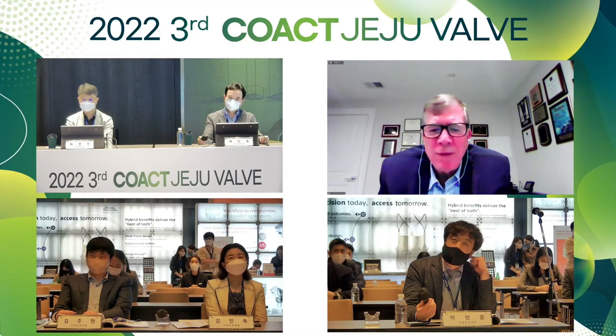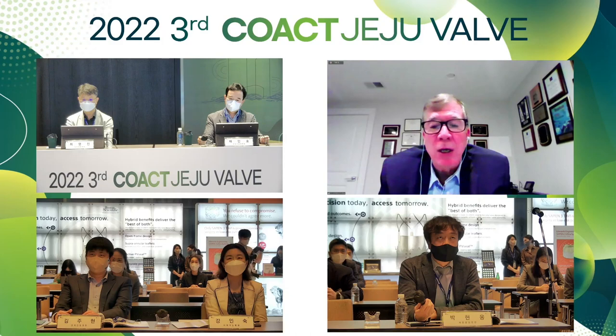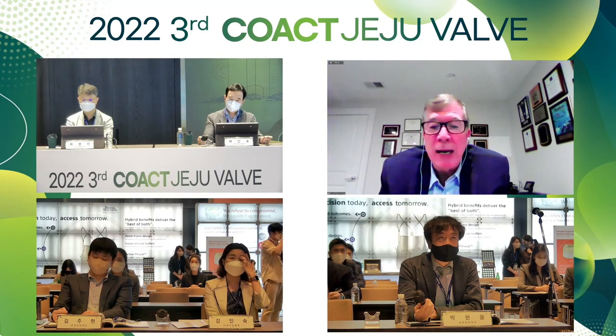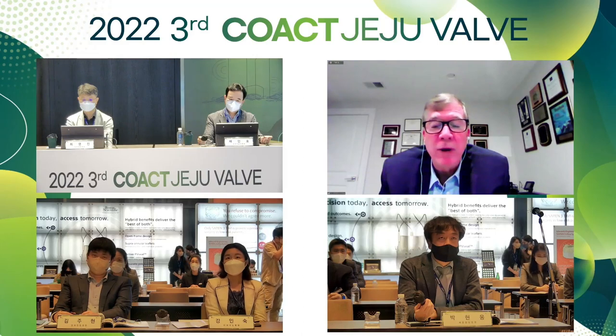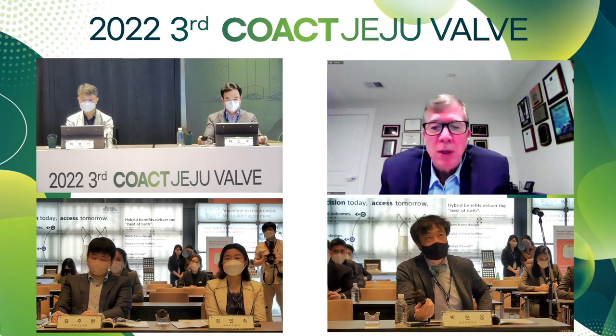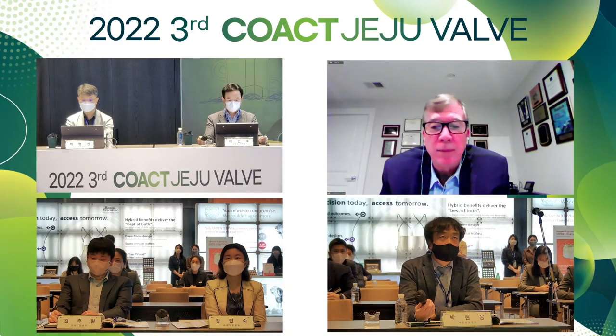Now, with respect to FX, there's not a difference in the profile, but there is a difference in the nose cone. So the nose cone now is like a dilator, like a sheath dilator, very smooth, so that you won't feel any resistance when you're entering into the common femoral that we may have felt with the older system. It's very atraumatic for the tip.